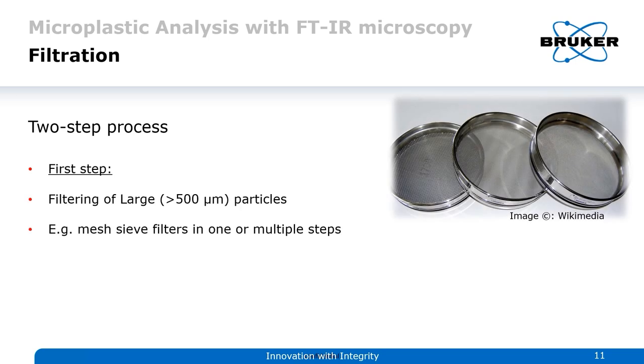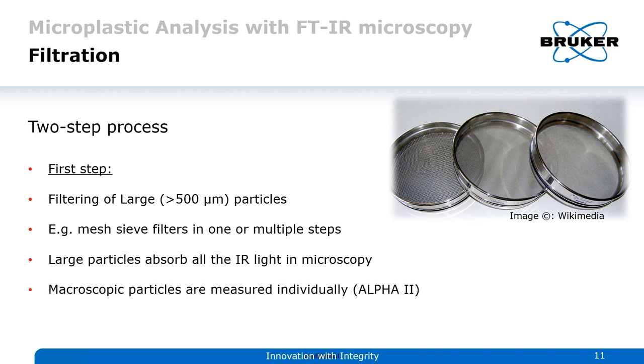When our sample is finally prepared, the remaining solution has to be filtered — mostly a two-step process. In the first step we filter off large particles, for example everything above 500 micrometers, using mesh sieve filters in one or multiple steps depending on particle sizes. We need to remove large particles because they absorb all the IR light in microscopy. For those we use the Alpha 2 spectrometer.